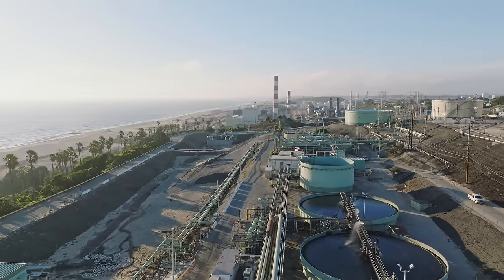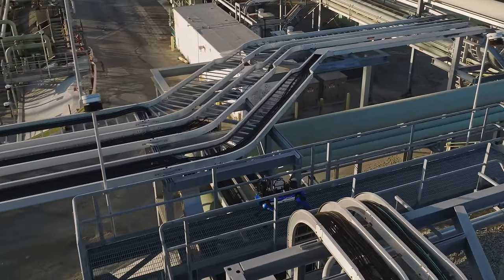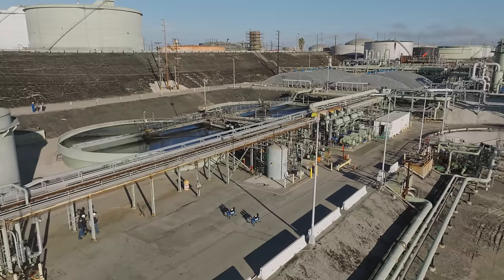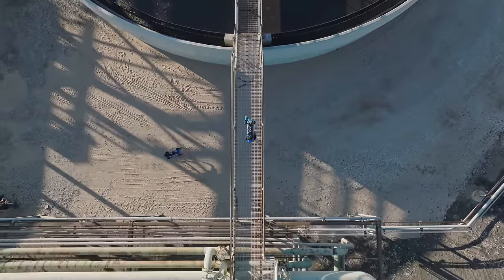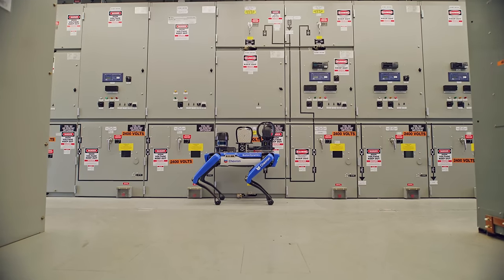One of our big ones here is ORD — operator routine duty — and it's the basic things you do every day: going around using sight, smell, and hearing to look at our equipment. Most of the time it's been qualitative and not quantitative, so we'd go around and say, 'Did this sound different? No? Cool, check the box.' But now with SPOT, we actually go take an acoustic measurement and then we can vet it. Same thing for temperatures — instead of 'is this hot or not?', we take a measurement and actually see and trend that data.